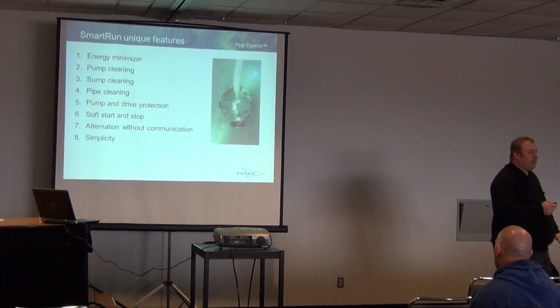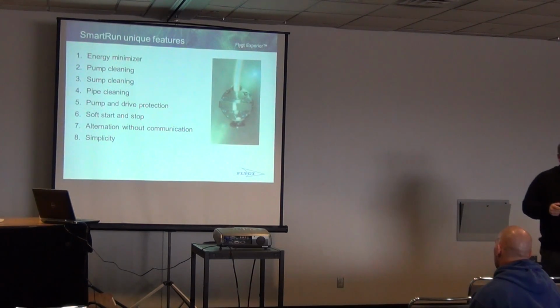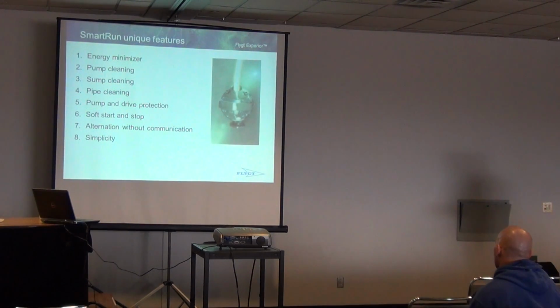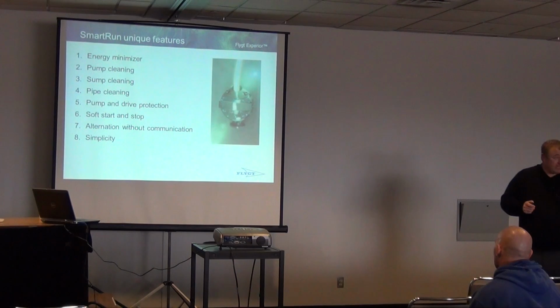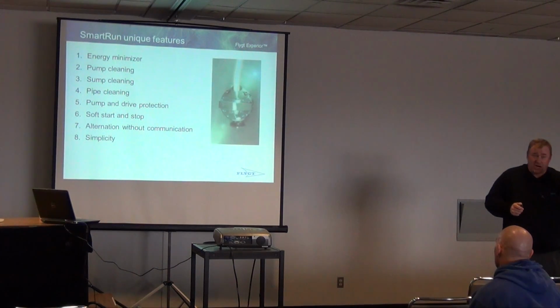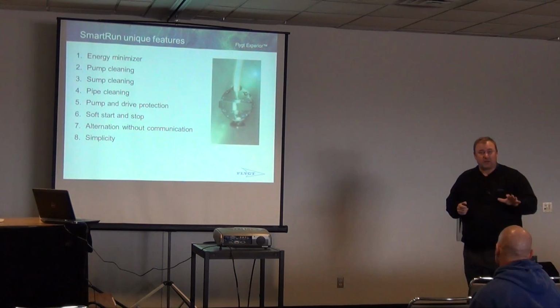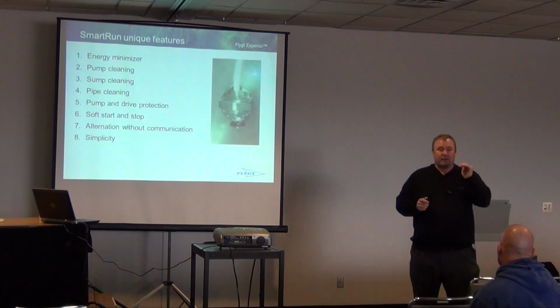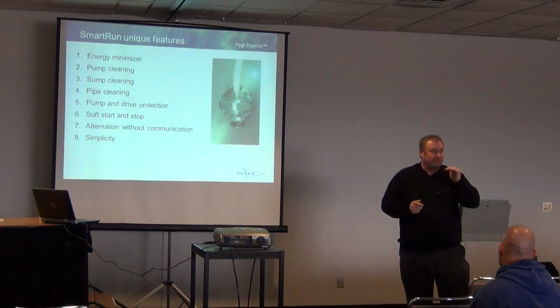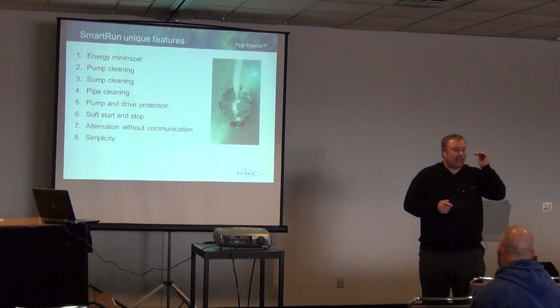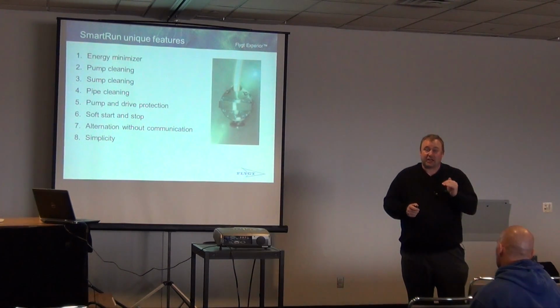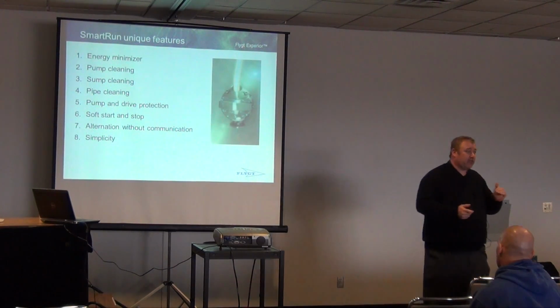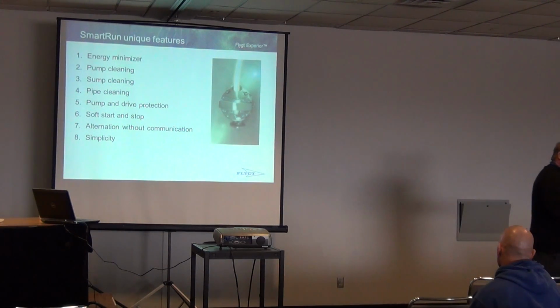So we will take that pump and run it to 60 hertz at least once every 24 hours or on every start, if you so desire, to clean that pipe, get it up to 60 hertz, full speed, 100% speed, and then we slow it back down to that point where you're actually maximizing your specific energy in that station. And that's where that energy efficiency and that cost savings is coming to you over time throughout a year.